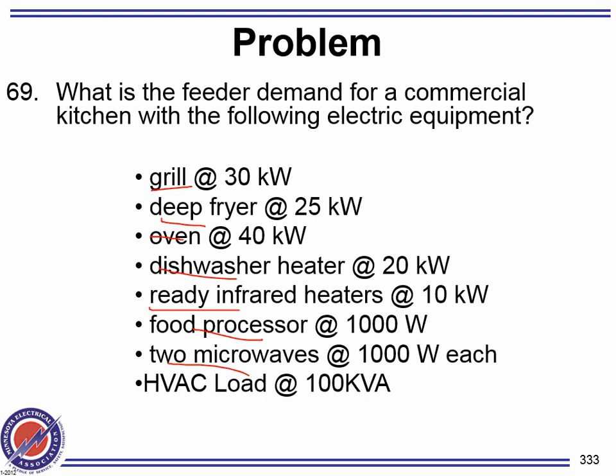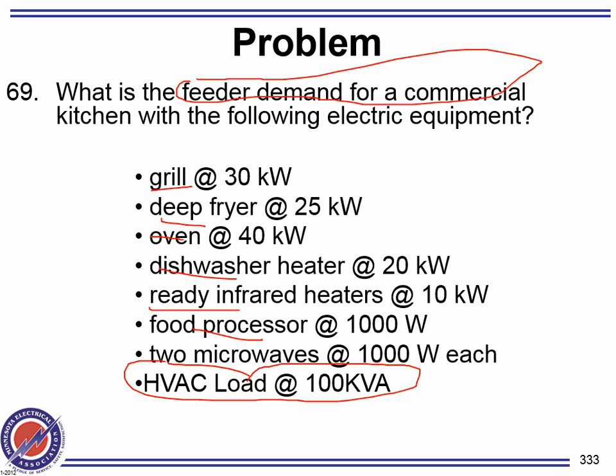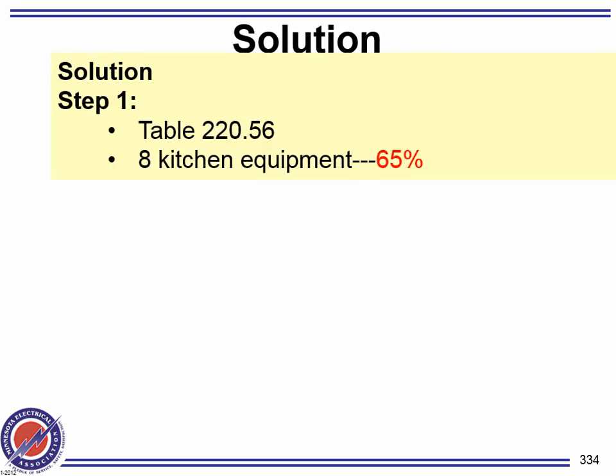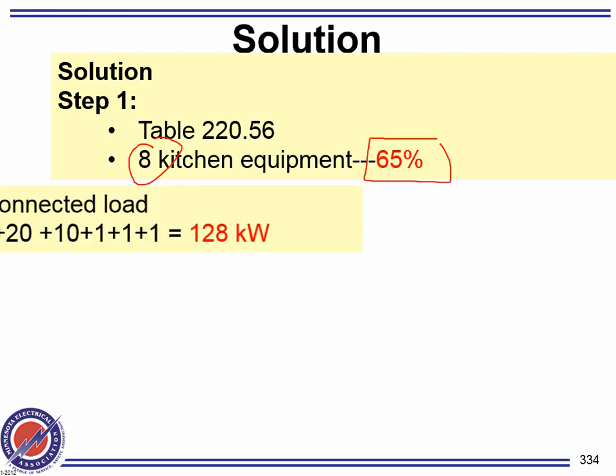Oops, how about this chunk here? HVAC, rooftop unit. Is that directly related to the preparing of the food? Okay, and they're asking about the feeder demand for this commercial kitchen. What's the feeder demand for this commercial kitchen? Okay, you're going to add just the equipment, guys. Add them all up, and don't add the HVAC. At the end, we'll add the HVAC. Everybody can see that. Okay, how many pieces of equipment do I have? 9 of them, 8 of them. For 8, what's my demand factor? 65.